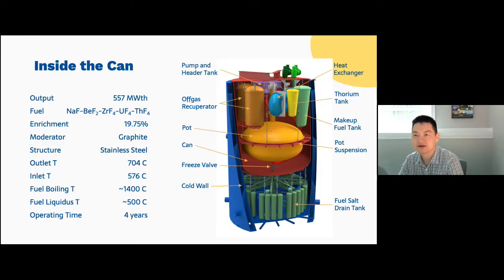So here's basically the top. There are two valves you can see here, which are part of the secondary loop. The secondary loop flows into the can on the tube side of the heat exchanger to transfer the heat. Whenever we need to replace the whole can, we cut off the valve here and remove the entire can as a whole.